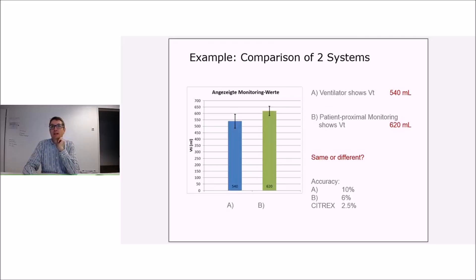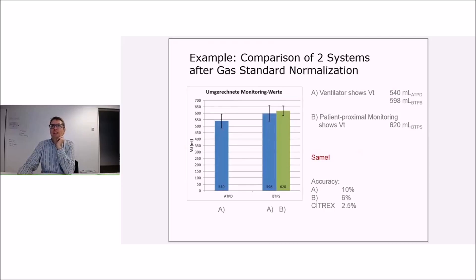So the final analysis was actually the root cause was the ventilator which was running in a different gas standard than the proximal flow measurement. It was running in ATPD showing 540, and the proximal flow sensor was measuring or displaying at 620 saturated. But when we compensated that to BTPS, it was 598. Together with the accuracy indices, and we can see that very nicely here with the uncertainties of the measurement, we could demonstrate that this was the same measurement.